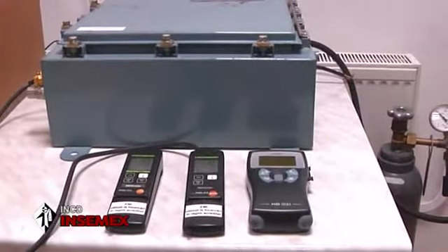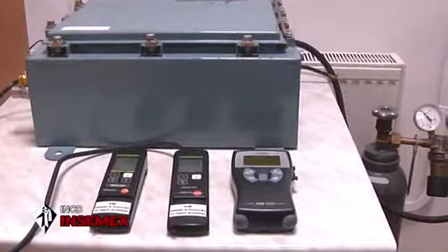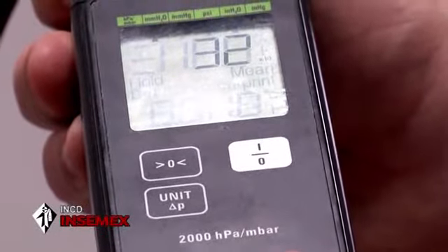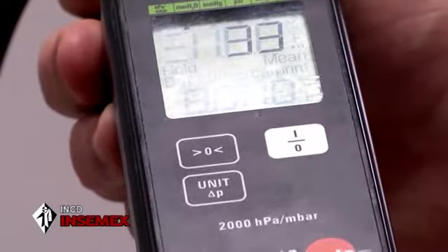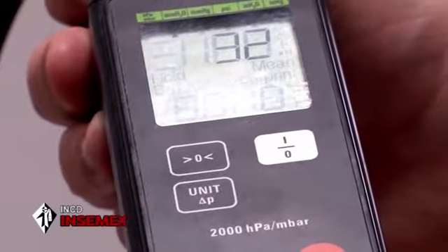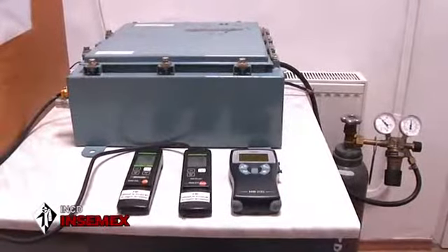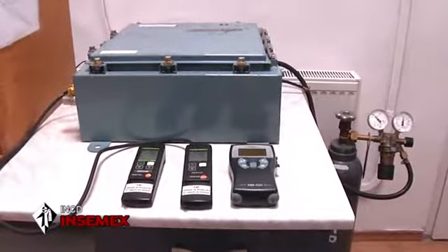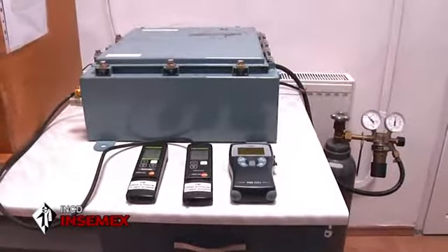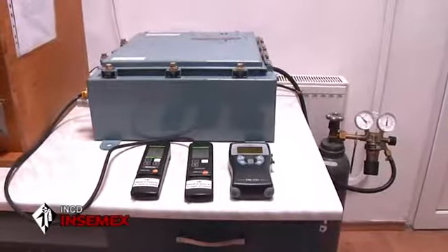Pressurized chambers come to cover the situations in which there is a large number of normally constructed equipment in a certain enclosure, and the cheap, fast and efficient solution is for the chamber to be pressurized. The minimum overpressure which has to be maintained during the entire operation time of the equipment and for a pre-established time after is lower than the one for pressurized equipment, taking into account that in this case the intervention of the human factor inside the enclosure is also needed.